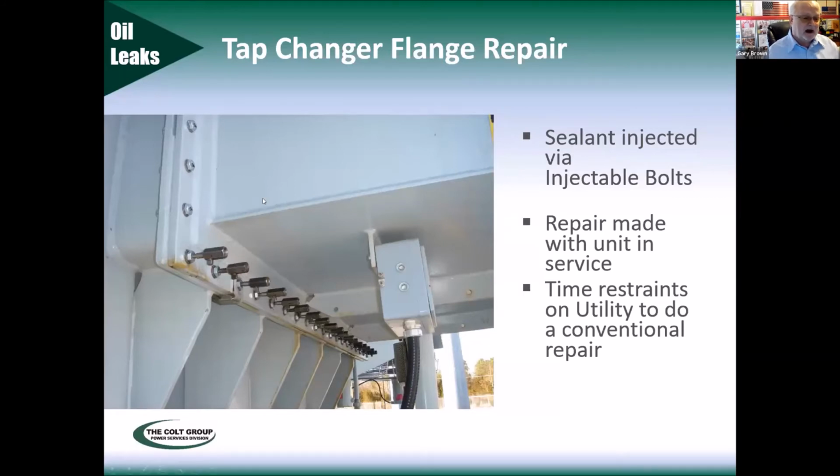But I said we don't use epoxies, we will use some in an instance like this because a lot of these flanges have a crush preventer bar in them that runs along here, so you can't overcrush your gasket, but there's spaces in them. So we want to make sure when we pump our sealant, it doesn't extrude out that space. So that's where we would use an epoxy to retain our sealant while we pump that groove on something like that. But you can chip that off of there at a later date too. It's not like you've injected the inside of that groove with a straight epoxy.